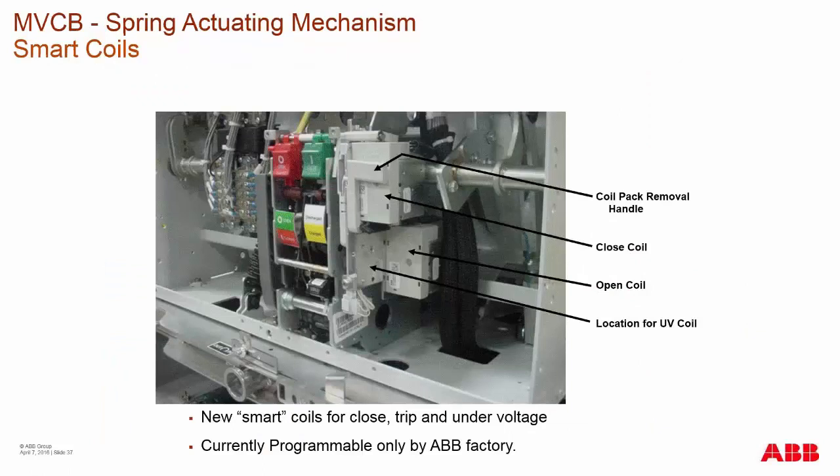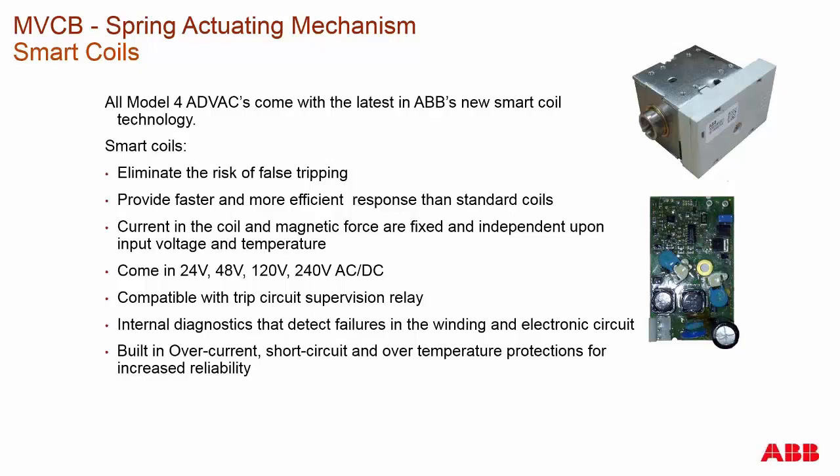The smart coil technologies applied to our EL mechanism breakers in both low voltage and medium voltage: it's very simple to remove your coils by removing a single screw and pulling the pack out, which contains the close coil, open coil, and under voltage coil. These new coils have a very low current draw with a small internal electronic board. This board makes the coil act like a standard coil of the past, where if there was a problem, it would open the circuit.